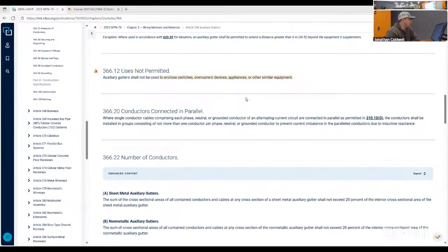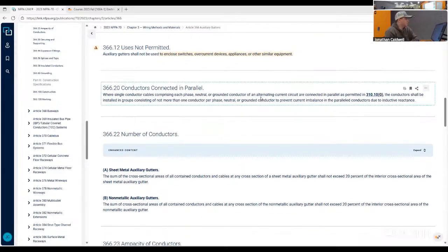Use is not permitted. Auxiliary gutters shall not be used to enclose switches, overcurrent devices, appliances, or similar equipment. Conductors connected in parallel. Where single conductor cables comprising each phase, neutral, or grounded conductor of an alternating current circuit are connected in parallel as permitted in 310.10(G). The conductors shall be installed in groups consisting of not more than one conductor per phase, neutral, or grounded conductor. Prevent current imbalance in parallel conductors due to inductive reactance. Who can tell me what that is saying?